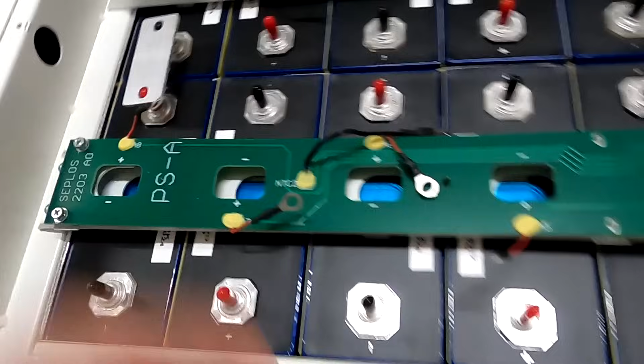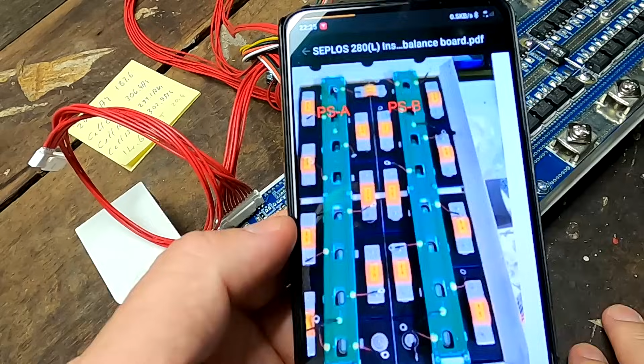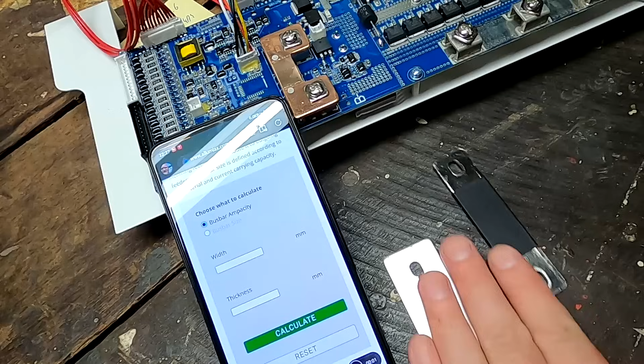Because this is tinned copper, while these ones are aluminium bus bars. Or should we use the aluminium bus bars which are coming with the box? I'm not sure. And the manual, I think they are flexible bus bars, right? Yes, they are. You can see it here at the end. So in the sample and the manual, they're using flexible bus bars, which is correct. But they're supplying only these cheap aluminium bus bars.